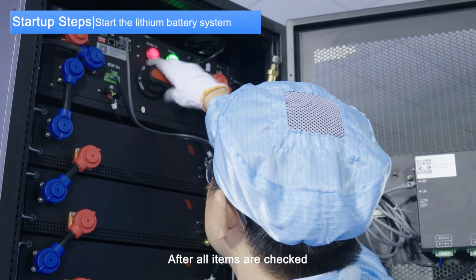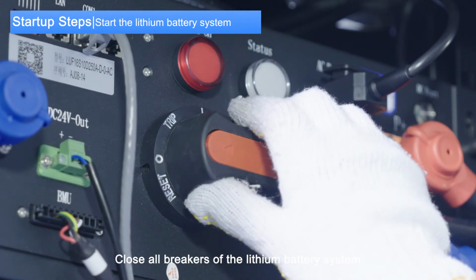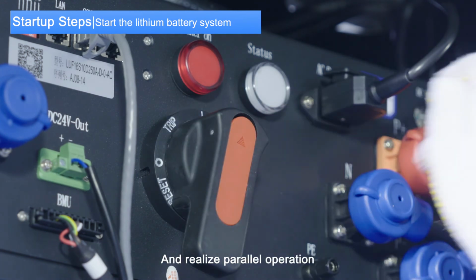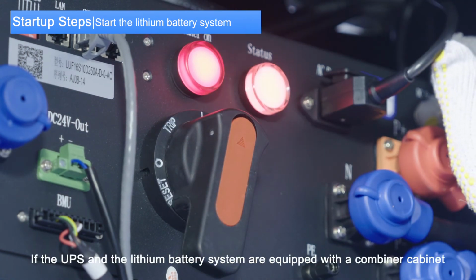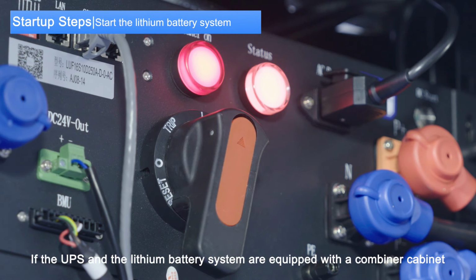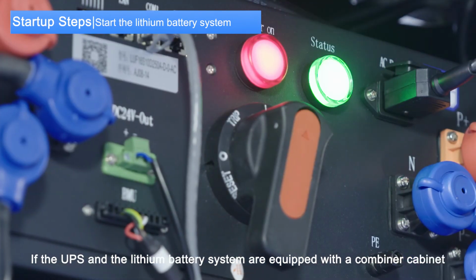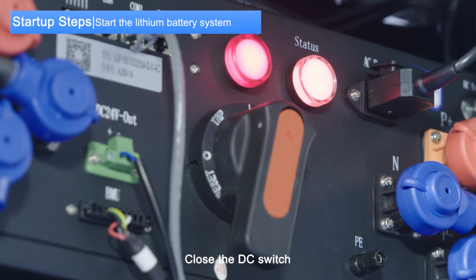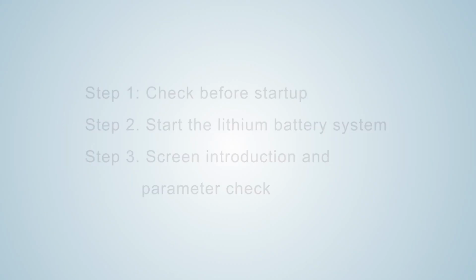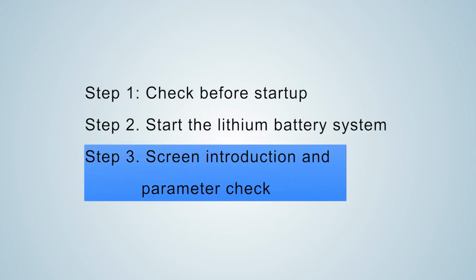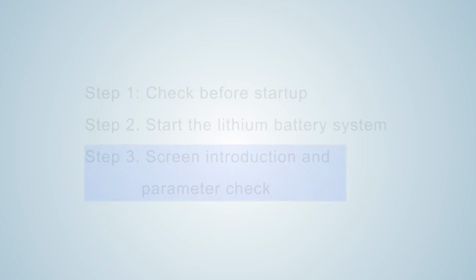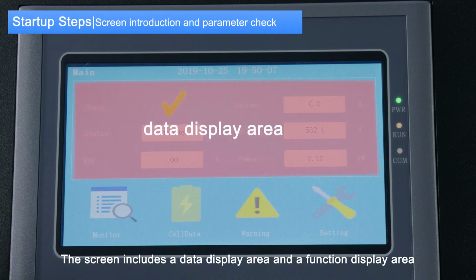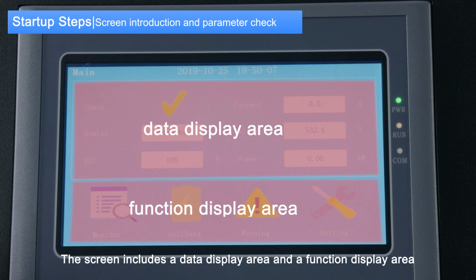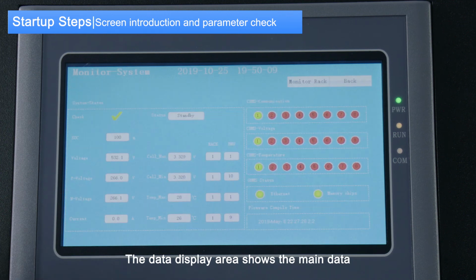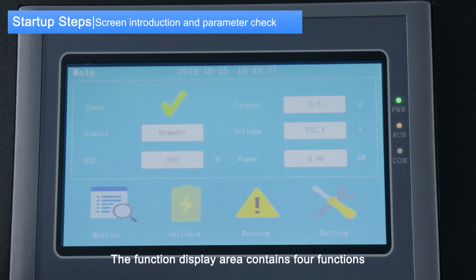3. After all items are checked, close all breakers of the lithium battery system and realize parallel operation. 4. If the UPS and lithium battery system are equipped with a combiner cabinet, close the DC switch. Step 3. Screen introduction and parameter check. 1. The screen includes a data display area and a function display area. The data display area shows the main data. The function display area contains 4 functions.